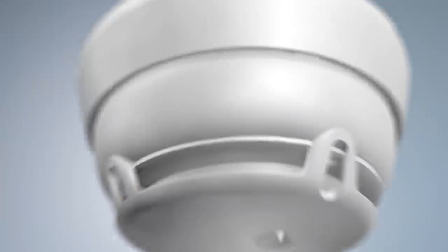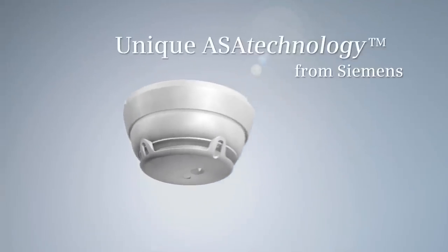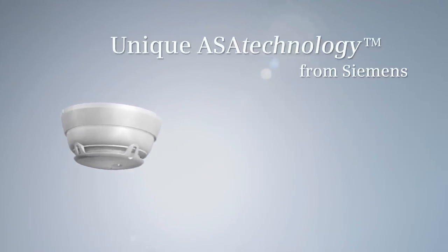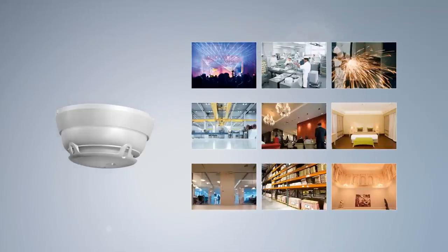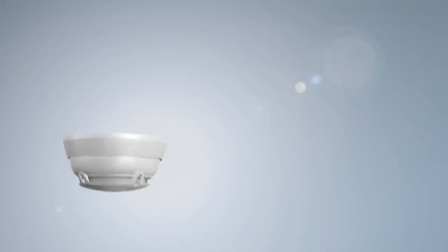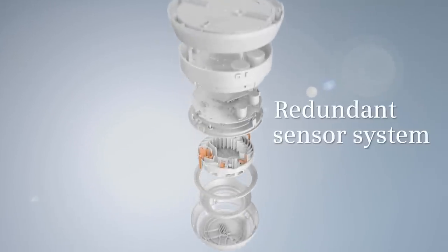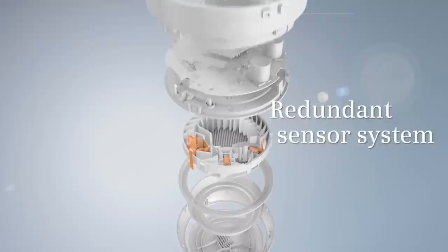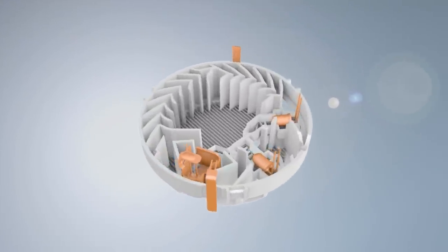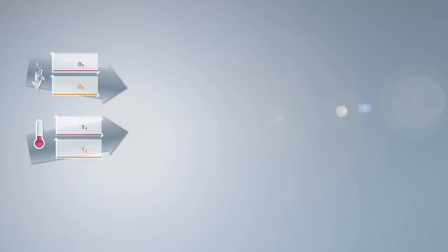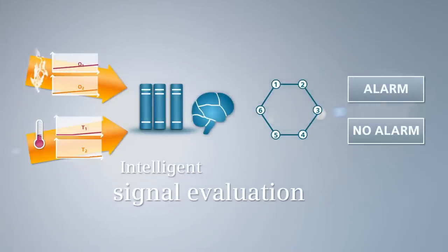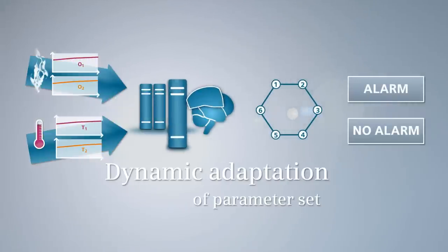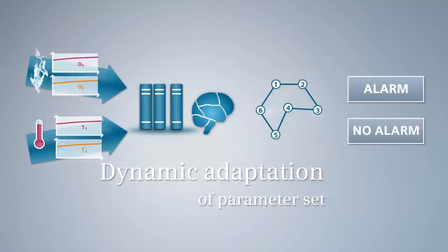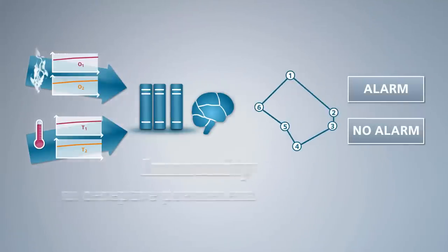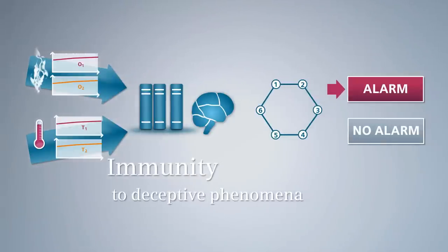The Swing detector with the unique ASA technology provides highest detection reliability for any application. The detector has a redundant sensor system with 2 optical and 2 heat sensors. ASA technology evaluates the signals in real time and dynamically adapts the selected parameter set. Thus, the detector is immune to deceptive phenomena such as dust or steam.